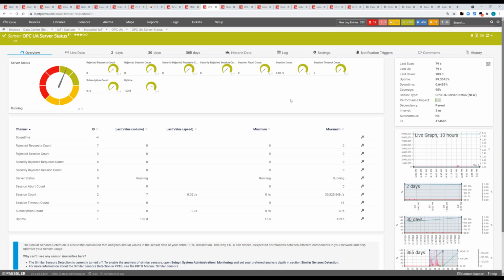On the other hand, we can also address some security concerns, because we can monitor the session count. When you run usually like 4 OPC UA sessions in your network, and now you have 7, you should be aware of that, because there are 2 connections you are not aware of, and you should find out who's connecting to my devices. Same on the other side, when you usually have 4 connections and now you have only 3, you should get an alert, you should be aware that 1 connection failed, and you can instantly react. Also, we can represent the security rejected sessions. I think it's also very important that you get this data so you can really pinpoint issues in your production environment.